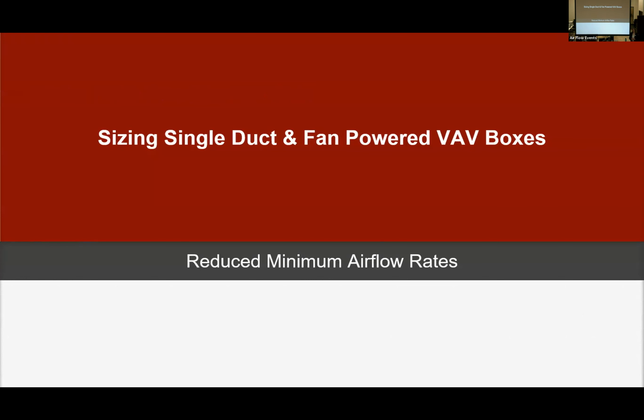Are there any questions so far on single ducts, airflow measurement? Does everybody get the whole thing, when the damper is nearly closed and then you open it a little bit, it doesn't really control all that well? It's like a quick opening percentage of butterfly damper thing. Yeah, most controllers and actuators are not smart enough or high tech enough to control these little percent changes. If you were to shrink that valve a little bit, now we're operating in a range that's kind of a larger sweep than this little guy is. You'll have less fluctuation and bouncing with a smaller valve.